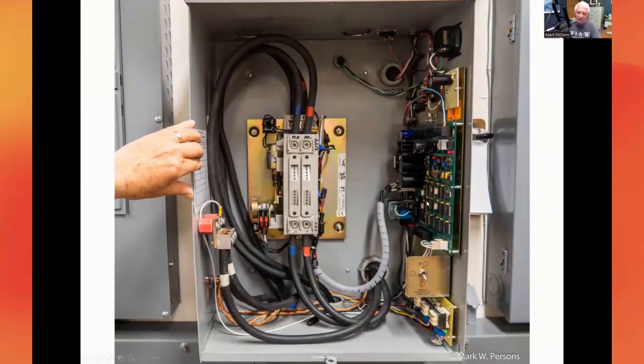Then it looks at the signal from the generator, the 60 hertz, 240 volts, and only when it's got to 60 hertz, within 1 hertz, I think, and the right voltage, will it then switch the power to the building. Let me show you the wiring. City wiring comes up here in the middle, goes up to the relay where it's labeled city, and then the output part comes down slightly to the left, and then the generator power comes in from the rear and plugs into the gen part of the relay. And the neutral is isolated as required by the rules.